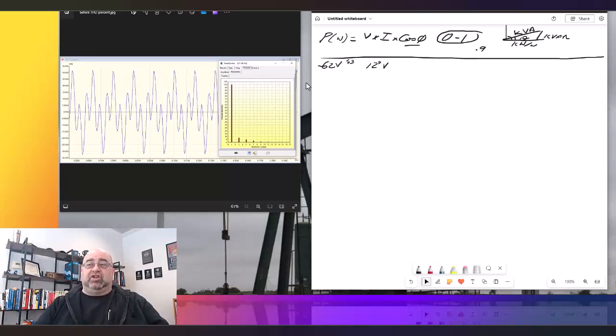In addition to what we're covering, which is the actual losses and emissions, all these crossovers affect all of the other systems. This is a cryptocurrency site, so all of this — I mean it's so bad that the neutral harmonics are pure, pure 180 hertz. Those became interesting, because when we started fixing all that, we got a reduction in total energy of somewhere around 6% so far, just through basic applications at the transformer and then ground.